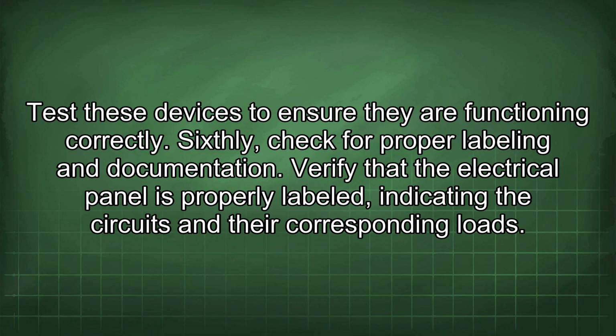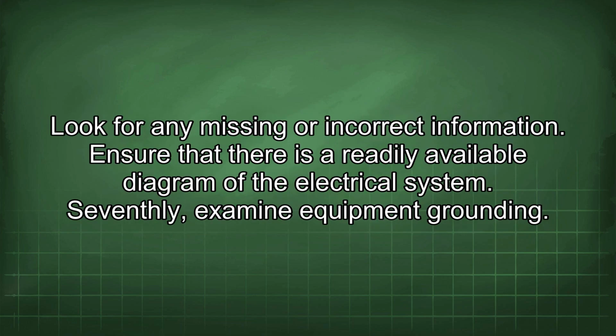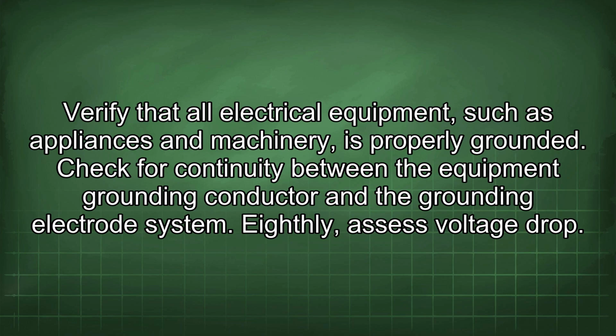Sixthly, check for proper labeling and documentation. Verify that the electrical panel is properly labeled, indicating the circuits and their corresponding loads. Look for any missing or incorrect information. Ensure that there is a readily available diagram of the electrical system. Seventhly, examine equipment grounding. Verify that all electrical equipment, such as appliances and machinery, is properly grounded. Check for continuity between the equipment grounding conductor and the grounding electrode system.